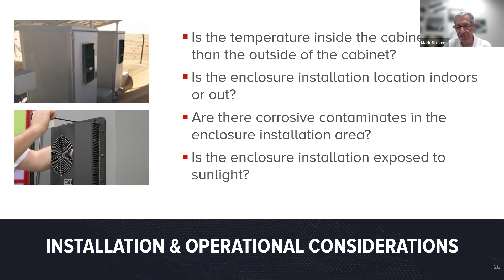And then is the enclosure installation located indoors or out? That may affect the NEMA rating of the product you pick. Are there corrosives or contaminants? Then you'd need to pick something like a NEMA 4X product. And is the enclosure installation exposed to sunlight? As Devin showed in the one picture, and as you go through different calculations, insulation is your biggest friend for solar loading. Just a half inch or a quarter inch of insulation makes a huge difference in the wattage you would require for cooling and installation.